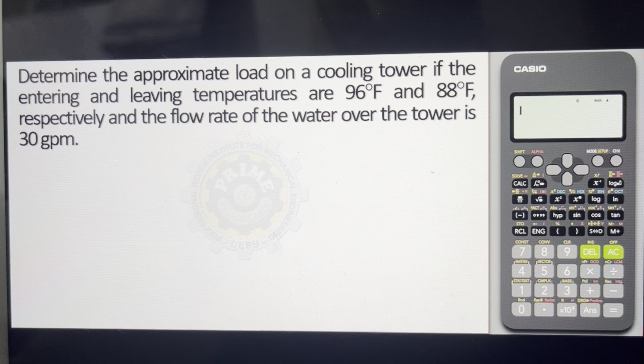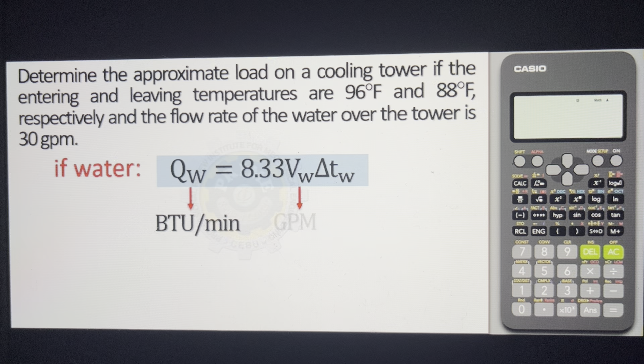Hindi ko na i-derive muna ha. The heat of water, the cooling tower load kung tawagin, is 8.33 times the volume flow rate of the water times delta T of the water, given that heat should be in BTU per minute, volume is in GPM, and temperature difference is in English units.